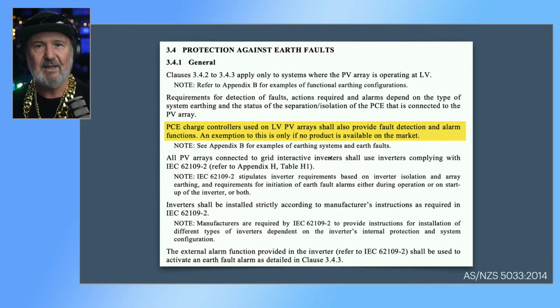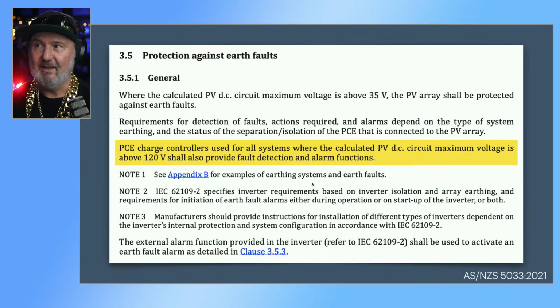Now, this is one of the most poorly complied with clauses, in my experience. I'll bring up some examples of it in a minute, but I don't want to be too harsh. And this is the 2021 edition, so it's dropped the word LV and said 120 volts, because in 5033 2021 we start referring to DVCs, decisive voltage classes. So this is the one time we're still talking about 120 volts, which is the old ELV, LV transition point. So charge controllers operating with PV arrays over 120 volts shall provide earth fault detection and alarm functions.